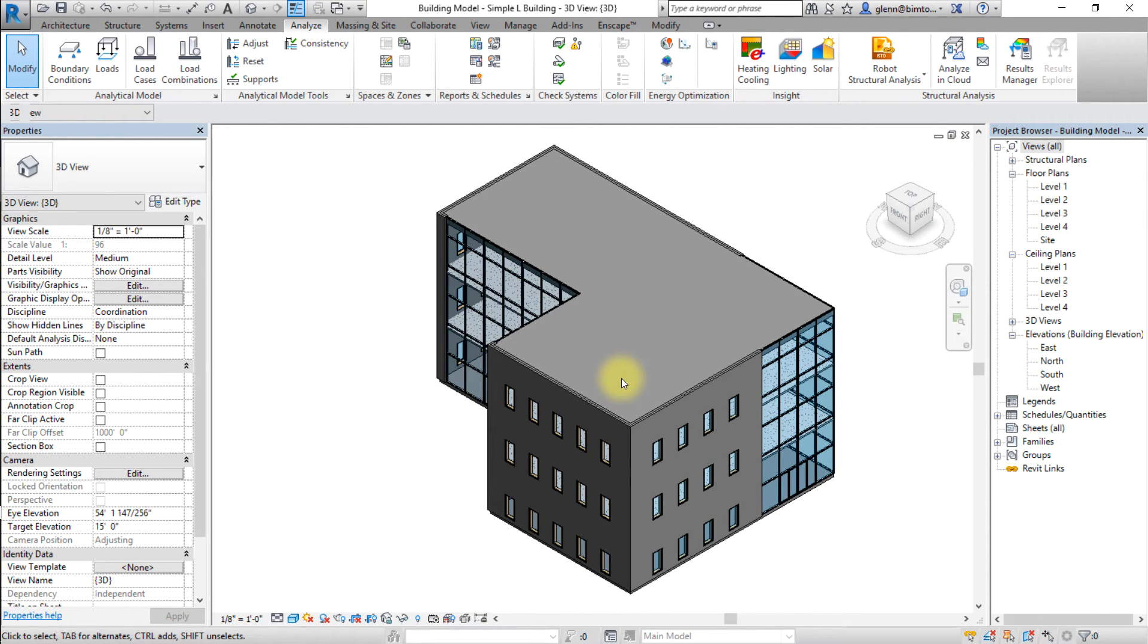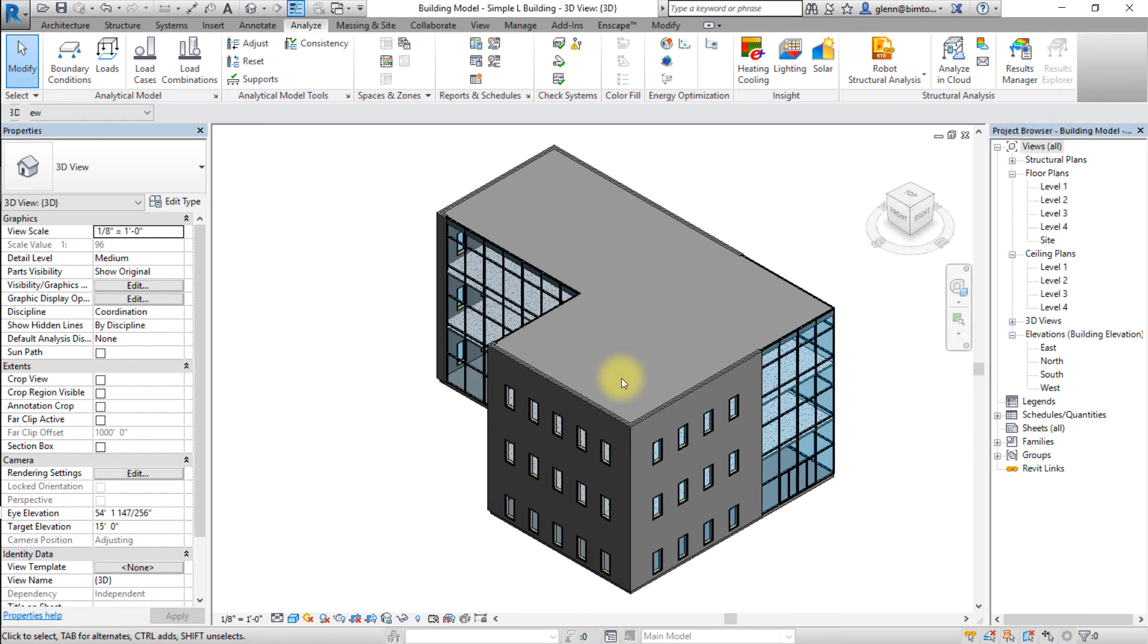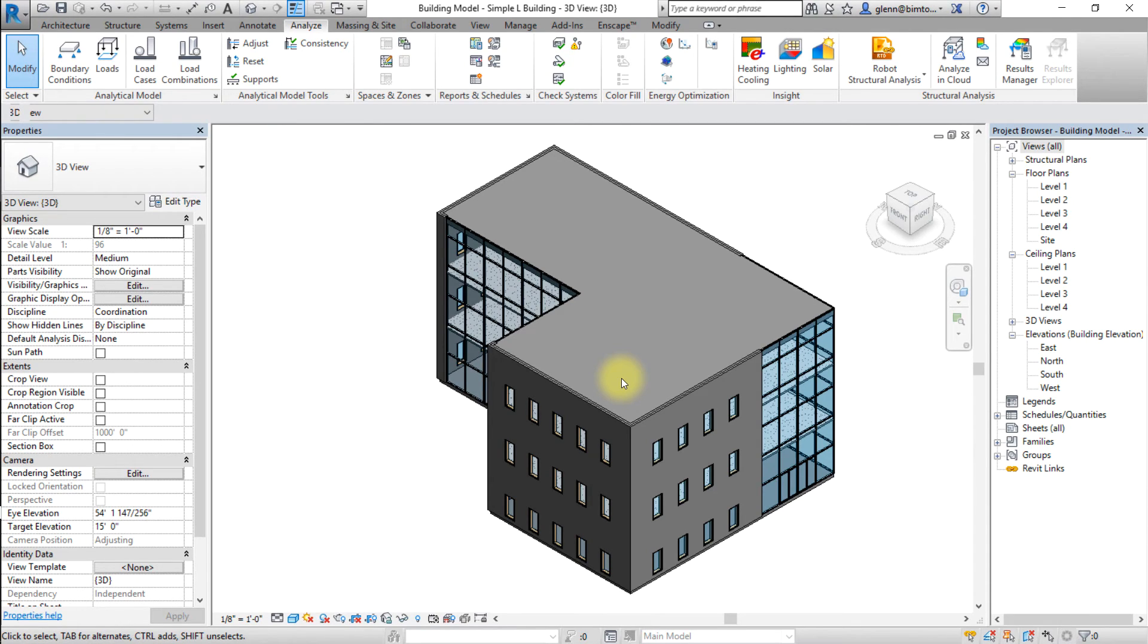If insight returns an error message indicating that the energy model cannot run successfully, try deleting extraneous detail from your model. Look for any elements that add geometric complexity, but will have minimal impact on the energy performance, such as interior walls or half walls that separate spaces that are in the same thermal zone.